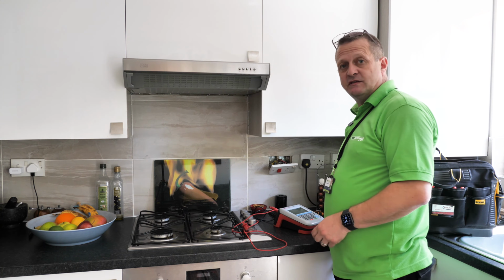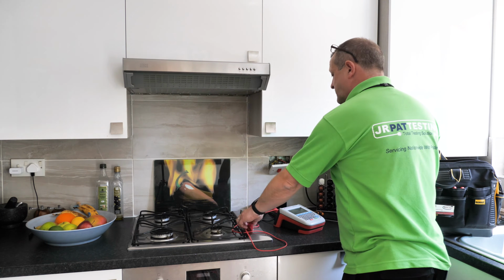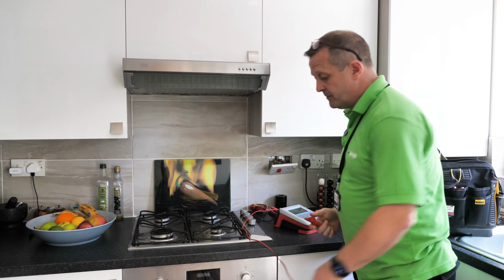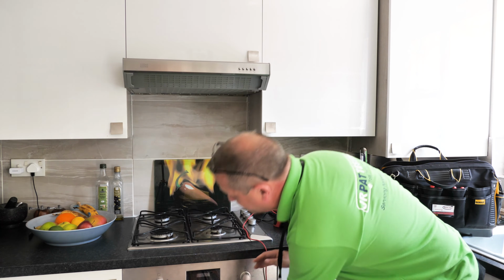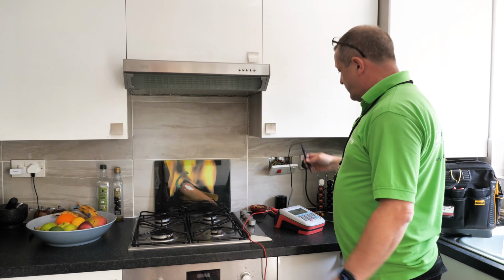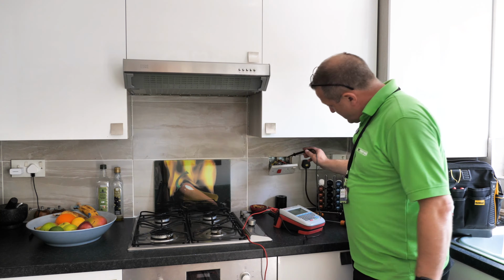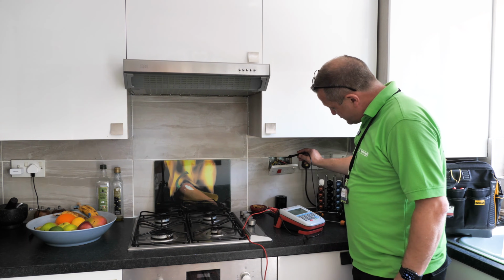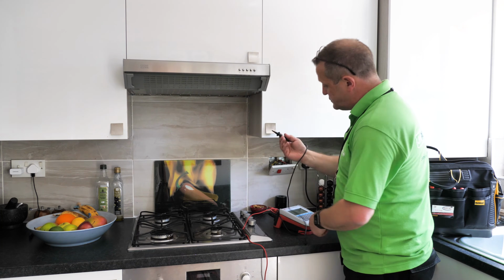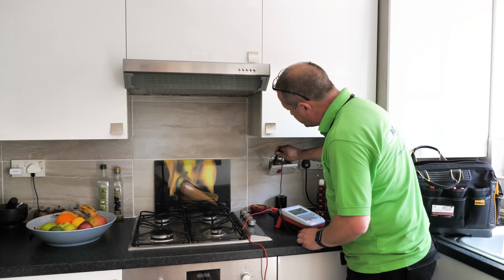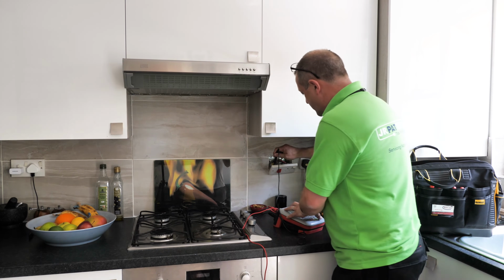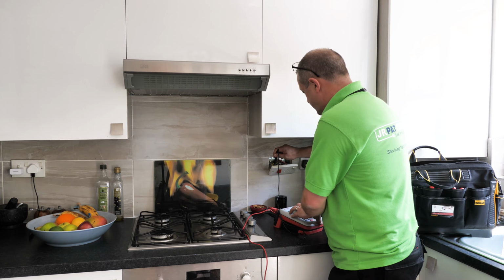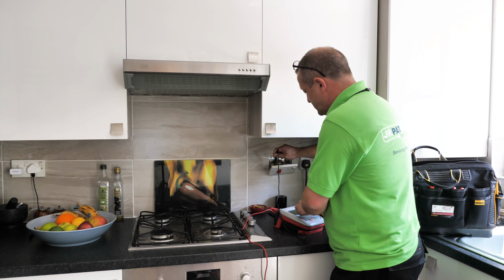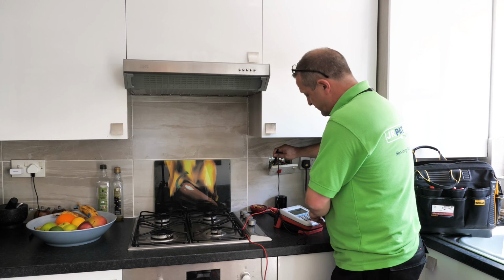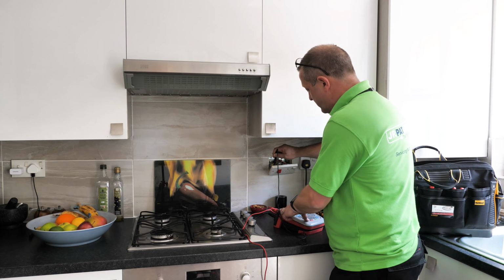The first part is the earth continuity test. In order to do this, we're going to take one probe with the crocodile clip and attach it to an exposed metal part, and I find the grill element on an oven works really well. And then with the other part of the probe, with the live and neutral cables separated, we're going to use the probe on the earth point and conduct the first part of the test. Conduct all the visual inspections. It's actually going to ask me to make sure that everybody is safe from the supply, and I'll continue with the rest of the test.